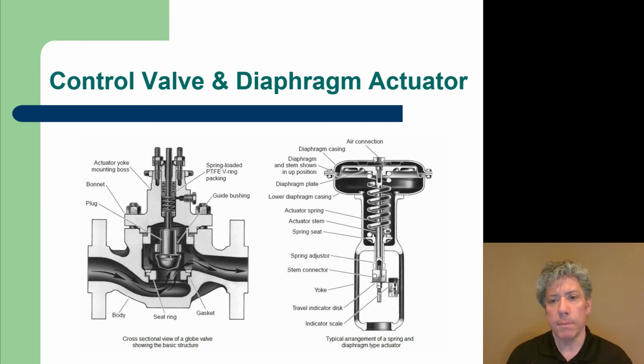Now, these valves can be a pain to deal with, but once you get them set up, they're very reliable and very, very good devices. One of the difficulties, if you look at the stem in the valve on the left-hand side for moving the plug in and out, is that the stem goes into the valve body, into the flow area, and so somehow you have to prevent the liquid or gas or whatever it is from leaking out through the stem, and so it requires something called packing. So you see in this case there's spring-loaded PTFE, which is Teflon V-ring packing. Now this packing has to be pushed in fairly tight, and so it provides a lot of friction against the stem. Of course they've used Teflon in order to minimize that friction and yet provide a good seal.